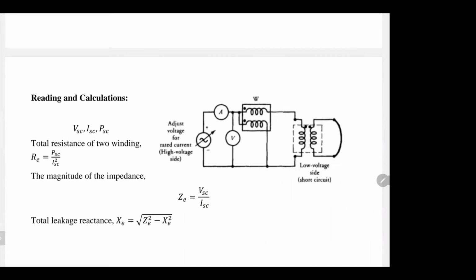Let's say that for the transformer in the lab, the rated current is 5 amp. If you apply the rated voltage with a reasonable resistance, it will draw the 5 amp. But if you make it a short circuit, the current will go to infinity, because voltage divided by 0 is equal to infinity. If you put just some resistance of the wires, 1 or 2 ohm, it's still high. It will blow the fuse. So what you do is put the voltage at 0 on the high voltage side and gradually increase it.